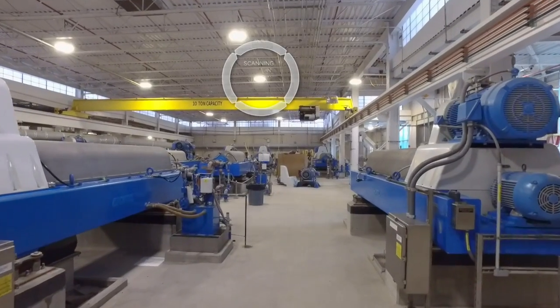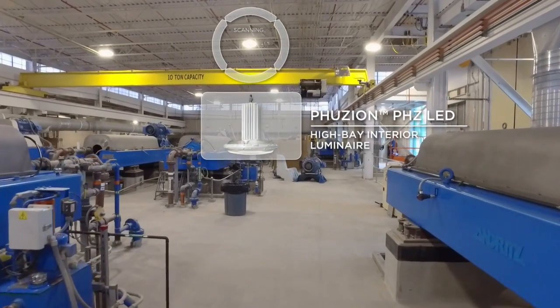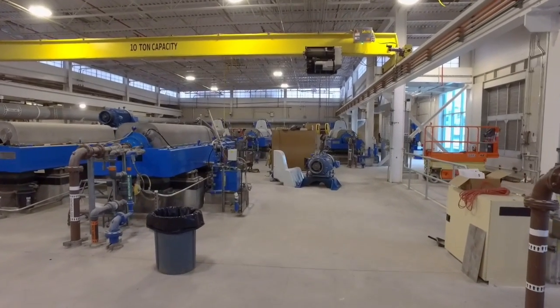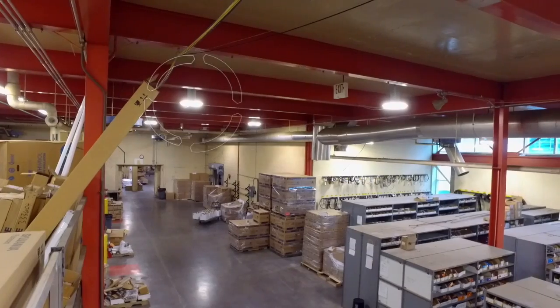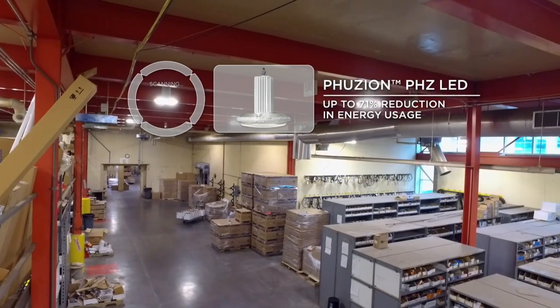Also in a lot of the rooms above ground — the maintenance facilities and storage facilities — they're using our Phuzion PHZ LED fixture, which is a really nice fixture. They replaced 400 watt metal halide, so you're going from a 400 watt fixture that uses 460 watts really, to a fixture that's 130 watts to 189 watts. So that's a huge energy savings.